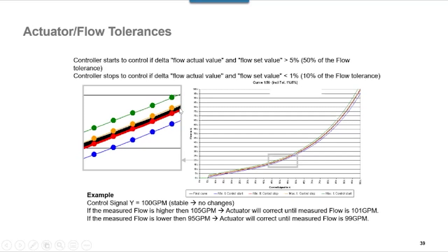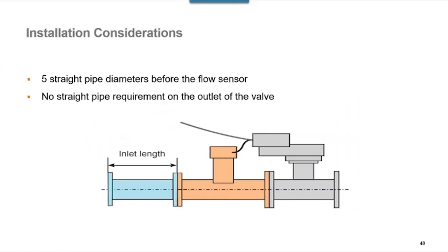The black line is the programmed curve of the valve in the actuator, with the plus minus 5% and the plus minus 1%. The valves do have linear curves built into them as well, if you can call it a curve. The linear characteristic built into them can be changed if you so need it, for instance, in a bypass application.